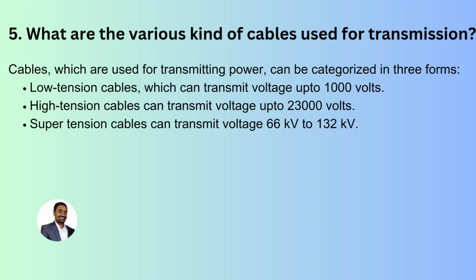What are the various kinds of cables used for transmission? Cables which are used for transmitting power can be categorized in three forms: low tension cables, high tension cables, and super tension cables. Low tension cables can transmit voltage up to 1000 volts. High tension cables can transmit voltage up to 23,000 volts, meaning 23 kV. Super tension cables can transmit voltage from 66 kV to 132 kV.